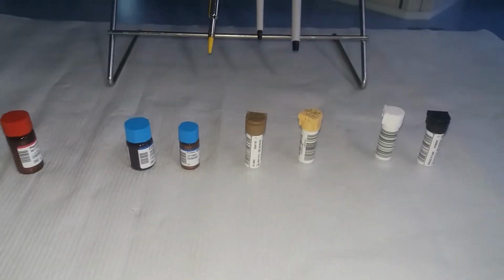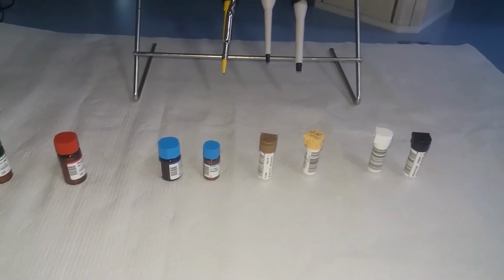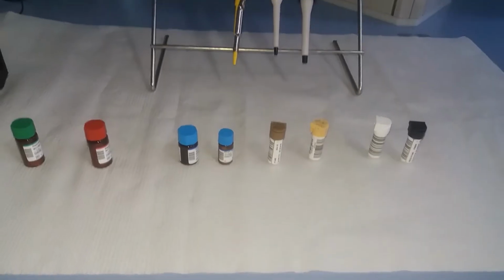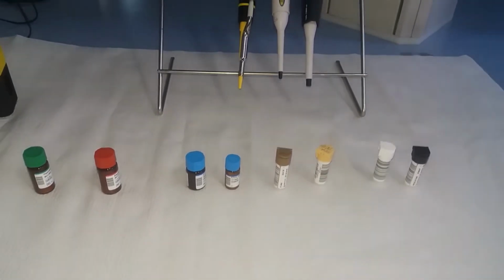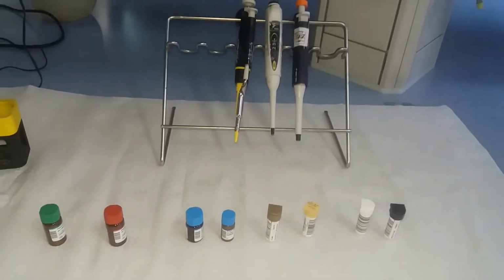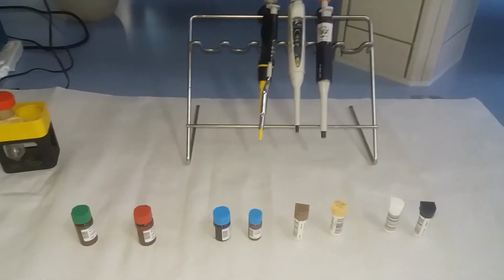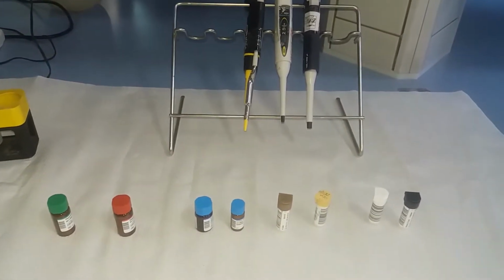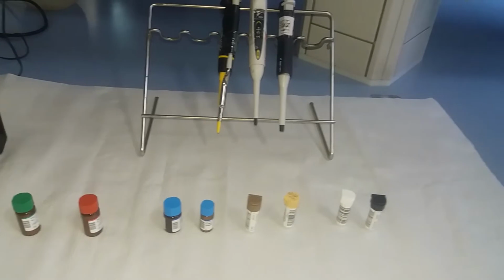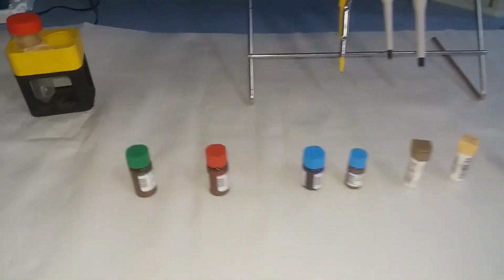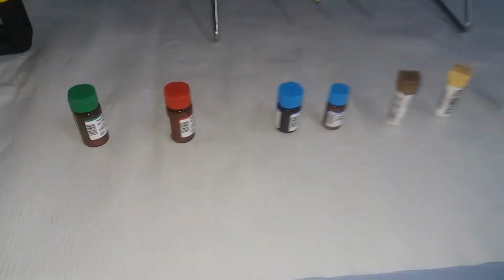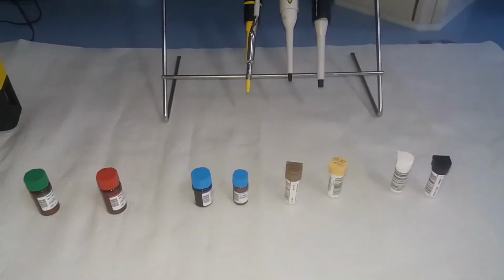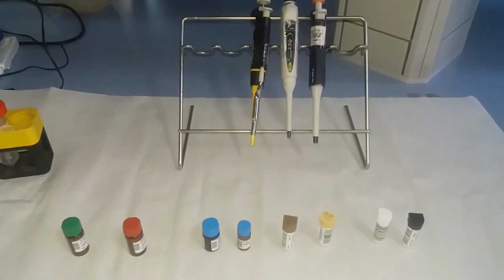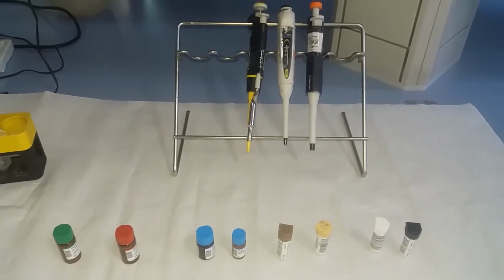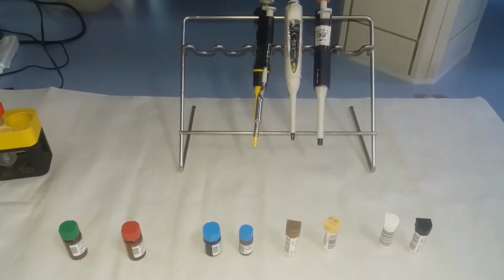Control preparation: the control can be prepared by adding the indicated volume of distilled water using a volumetric pipette, letting it sit for 30 minutes, and mixing carefully, avoiding foam formation. Before analysis, the control must be kept at room temperature before use. Writing the reconstitution date is recommended. Control must be within range. If out of range, repeating the run is recommended.